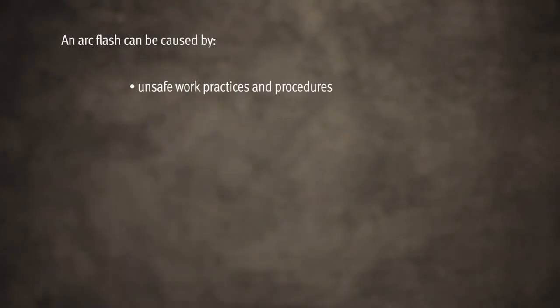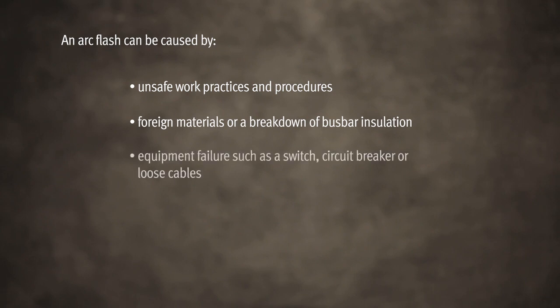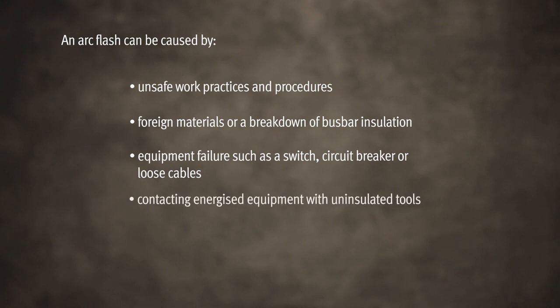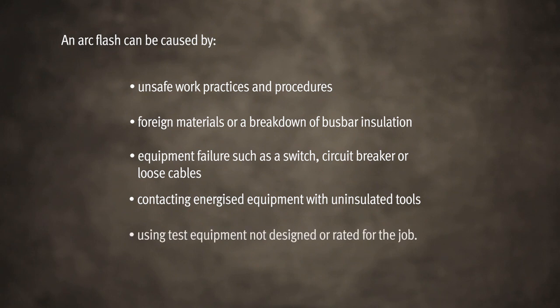This arc can self-sustain long enough to cause an incredible amount of damage to equipment and severe burns to anyone in the vicinity. An arc flash can be caused by unsafe work practices and procedures, foreign materials or a breakdown of bus bar insulation, electrical equipment failure such as a switch, circuit breaker or loose cables, contacting energised equipment when using uninsulated tools, or using test equipment not designed or rated for the job.